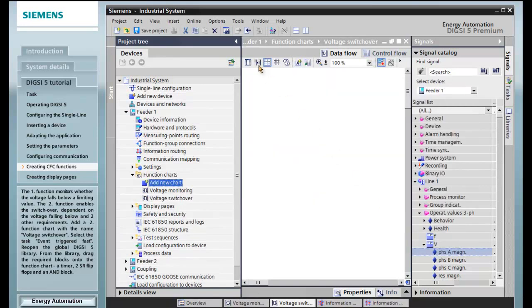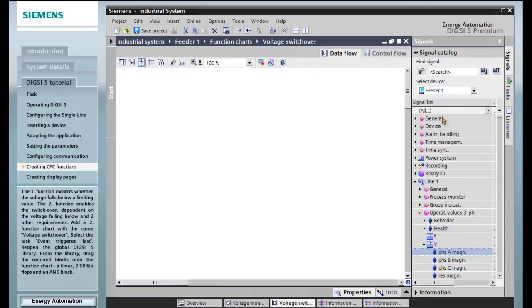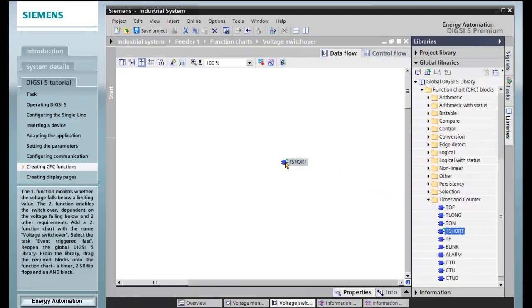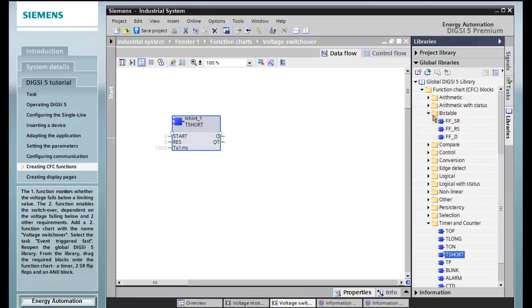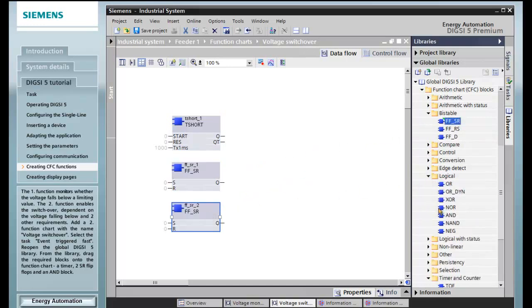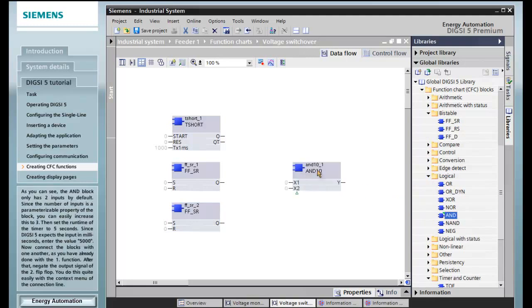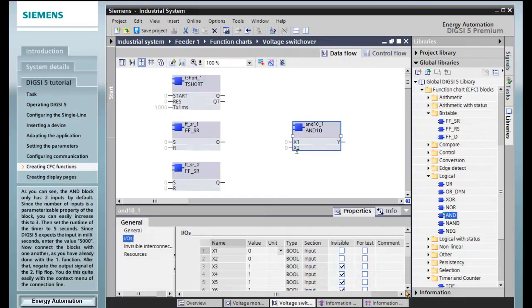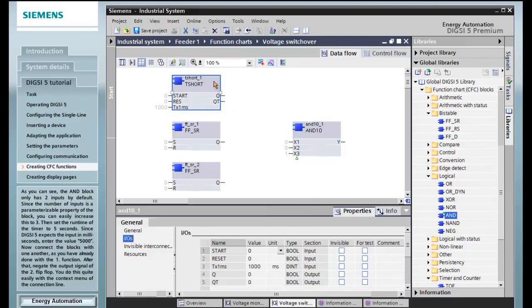You first of all have to reopen the global DIGSI 5 library. From the library, drag the required blocks onto the function chart: a timer, two SR flip-flops, and an AND block. As you can see, the AND block only has two inputs by default. Since the number of inputs is a parameterizable property of the block, you can easily increase it to 3. Then set the runtime of the timer to 5 seconds. Since DIGSI 5 expects the input in milliseconds, enter the value 5000.